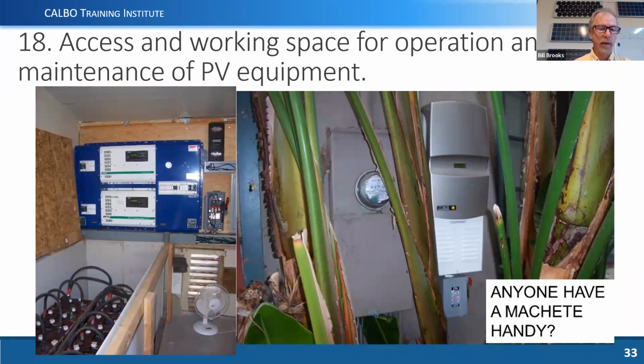So, but obviously it's better if you can do it from the beginning, have the full available workspace, and it's certainly a lot nicer to work on stuff when you have the full available workspace. On the left-hand side there, you see an old school battery system, and we're not going to see any of those installed in the last probably 8 or 10 years, but here you have a flooded battery. In order to work on this electrical panel over here, you'd either have to sit on top of the battery enclosure or stand in the battery enclosure, and then I would recommend not sitting down if you're standing in that enclosure. That could be kind of a hot seat right there.